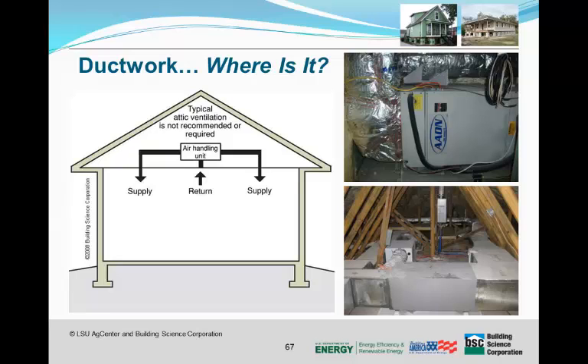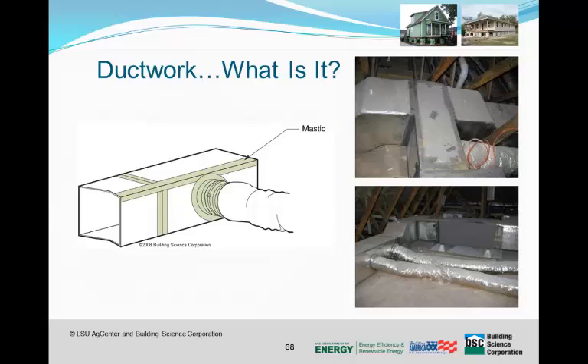And here, that's what was used in these homes, where the insulation was at the roof line, and that put the air handling unit and the ductwork within the insulated envelope of the building enclosure. What is the ductwork? By and large, insulated ductboard and insulated flex duct branches. So there was a central trunk and then branches that could have smooth, even curves, but everything was sealed tight with mastic, not with tape. Duct tape does not hold very long, and even the specialized UL approved tapes must be meticulously installed to manufacturer procedures and specifications in order to hold.